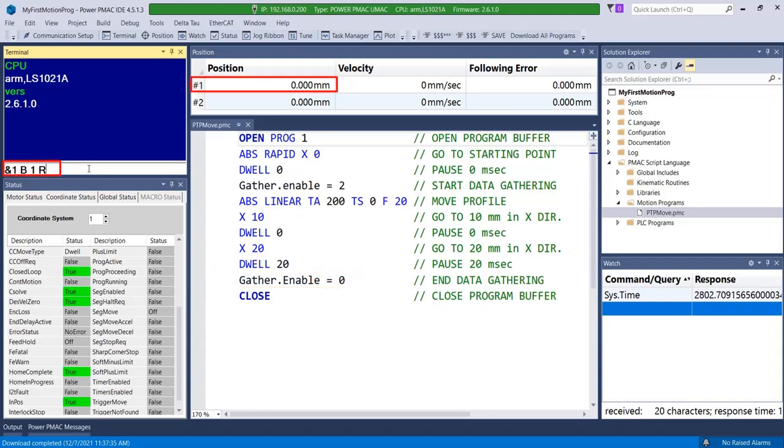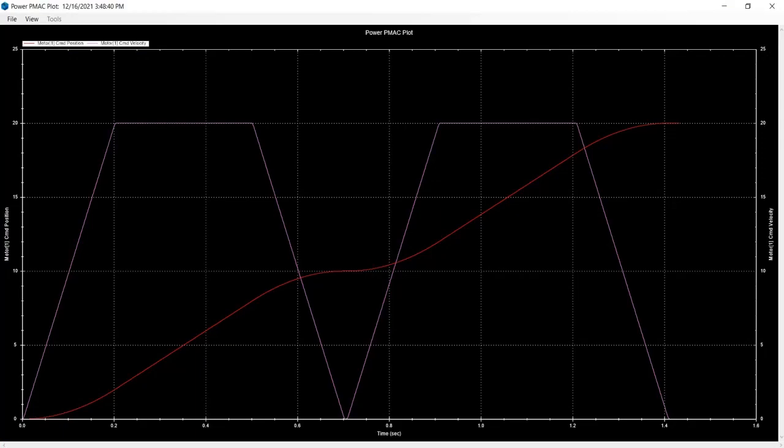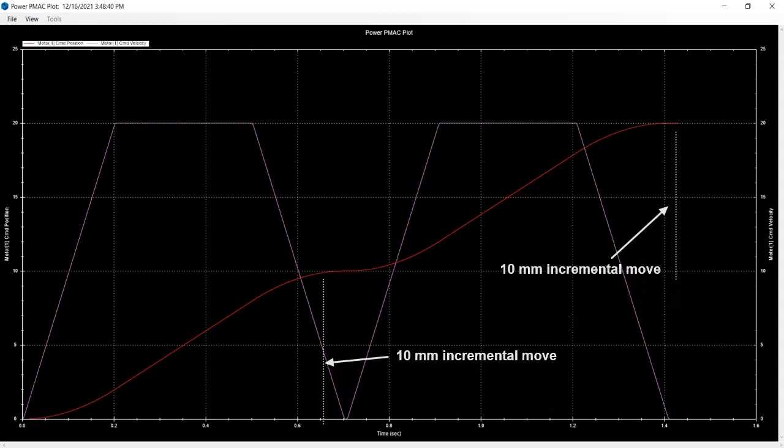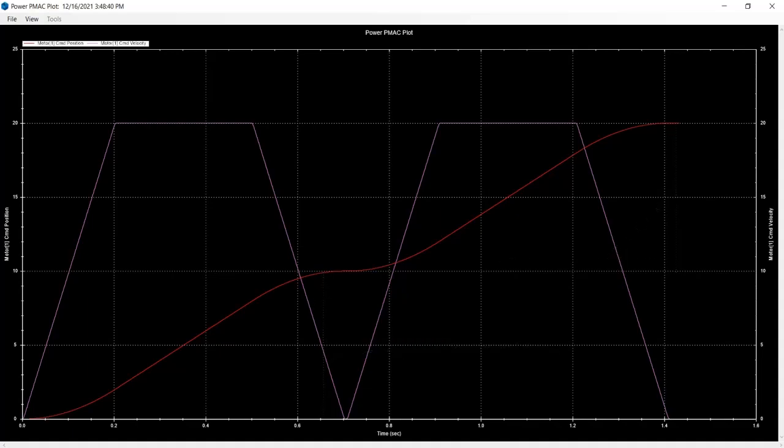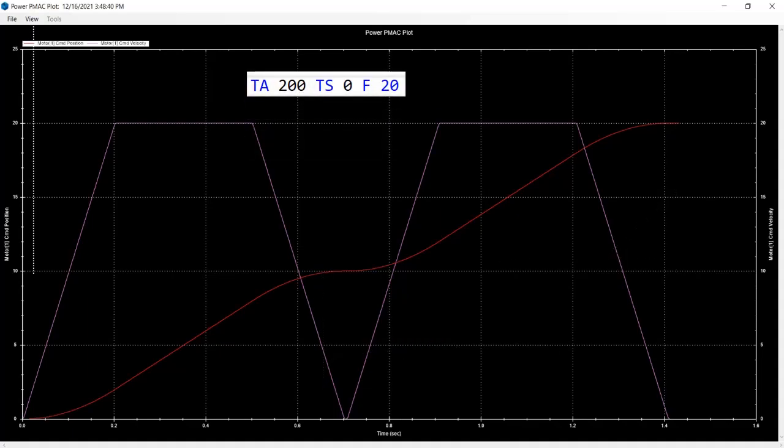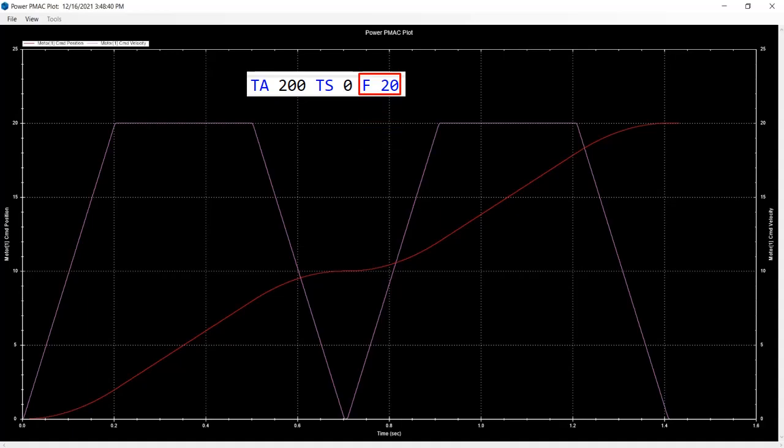Now let's run the program and take a look at the plot. This graph displays velocity in purple and position in red. The dwell between linear moves can be seen here as the motor is idle just before beginning the next move. The plot thus illustrates two sequential 10mm x-axis moves as designed by the program. On the velocity profile we see that the motor takes 200ms to accelerate as specified by TA. Since TS is 0, it doesn't extend the acceleration time or add any S curvature for smoother motion. As declared by the feed rate, the velocity reaches 20mm per second at the peak of each move.